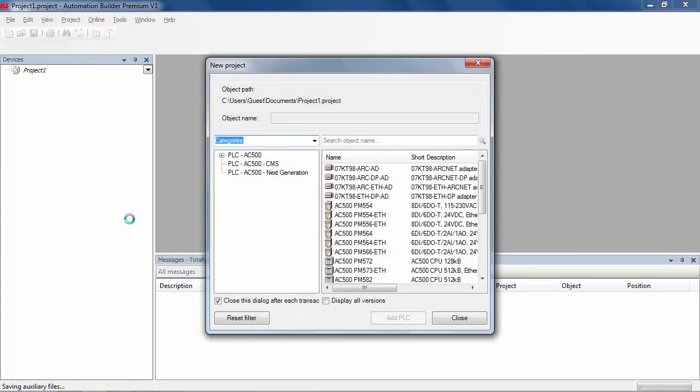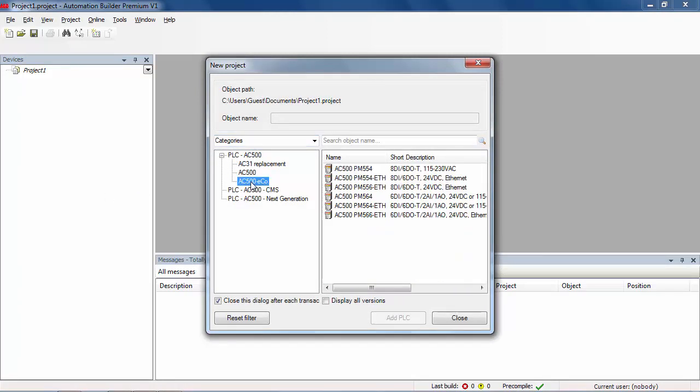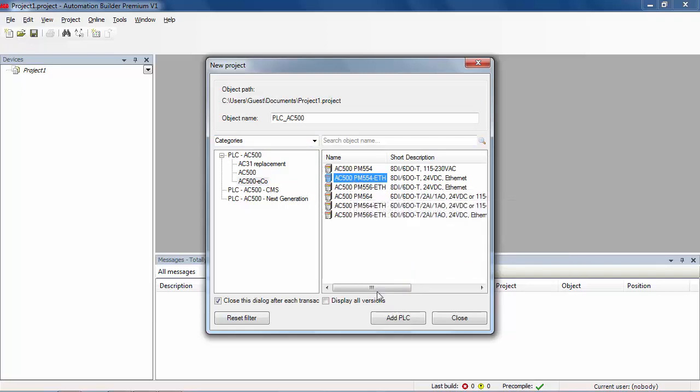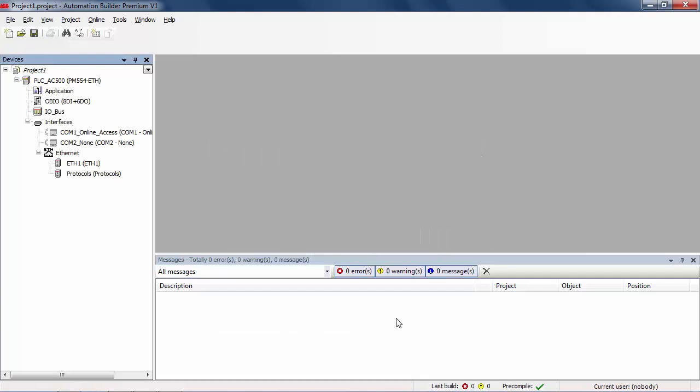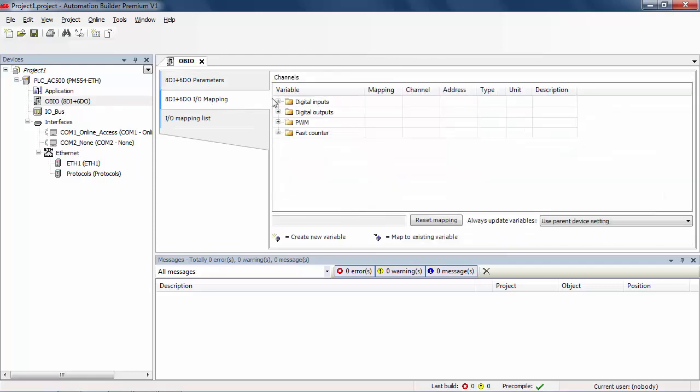Specify a project name and a location where this project will be saved in this computer. Then next, first select in the list the PLC device of your choice in AC500 ECO CPU range, here PM554 Ethernet. In order to demonstrate an exchange between AC500 ECO CPU and the CP600 ECO, we are going to use some onboard inputs and outputs present on AC500 ECO CPU. After selecting the module onboard IO, you will be able to configure the module and its channels, and then map its inputs and outputs using the IO mapping tab.